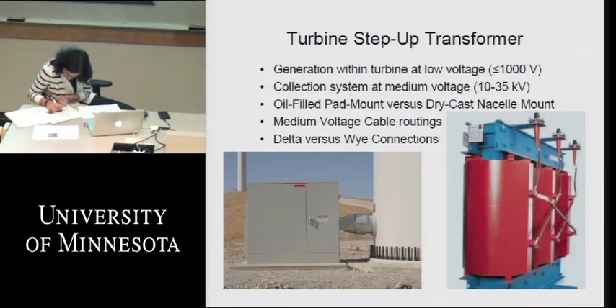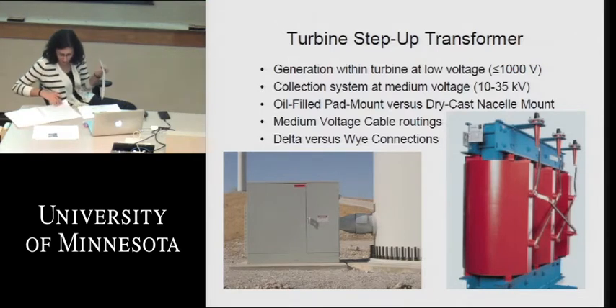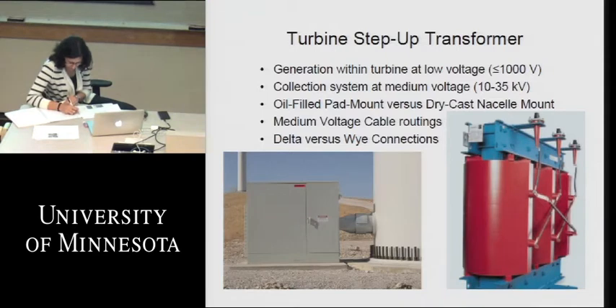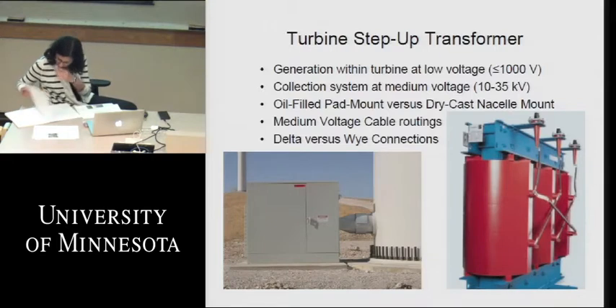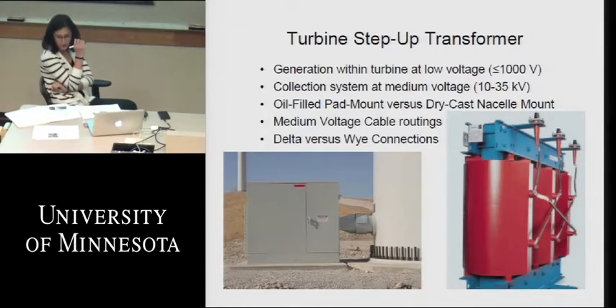If this was a 2 megawatt wind turbine, we could probably specify exactly a 2 megawatt transformer. Some engineers like to over-design it and put some extra margin into it, so maybe they might want a 2.10 or 2.15 MVA transformer for a 2 megawatt wind turbine, but they really don't need to. If you don't do the engineering design, then you really can't get away with it. But it's a simple calculation to include in your wind park design to say I accommodated for the cooling and extra cooling effect, and hence I can get away with a slightly smaller transformer.